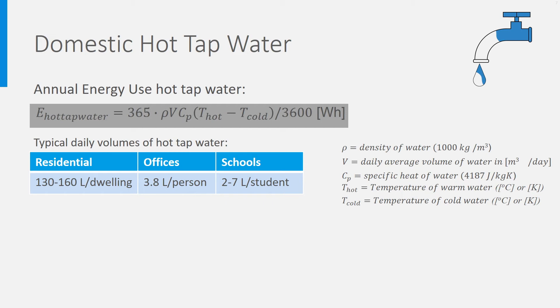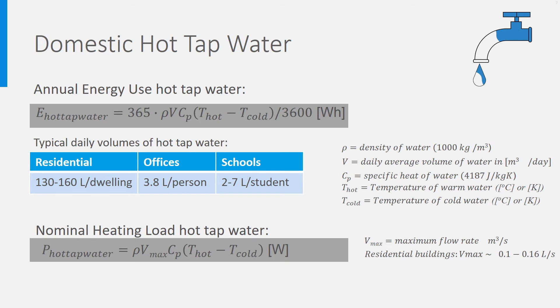Be aware that this estimate will be inaccurate on a daily level. A temperature T_hot of 45 to 50°C is enough to deliver hot water; however, many systems are continuously heated to 60°C to avoid the growth of legionella. Just like for space heating, you also need the nominal heating load — the peak load — to size the hot tap water equipment. This peak is obtained for the maximum volume flow rate, which is generally between 0.1 and 0.16 liters per second in residential buildings. The annual heating energy for hot tap water is much smaller than the space heating energy, but for peak load it is the reverse: the nominal power for hot tap water is generally much larger than for space heating.